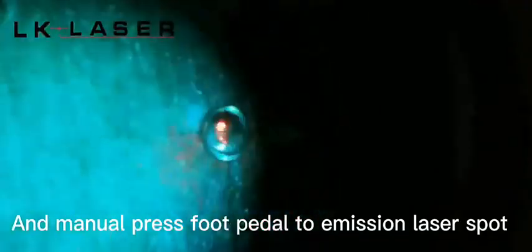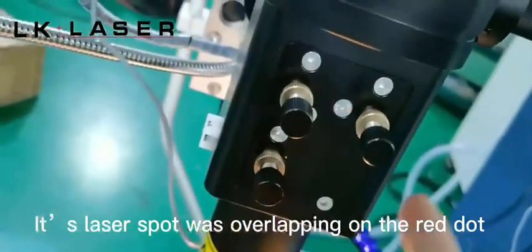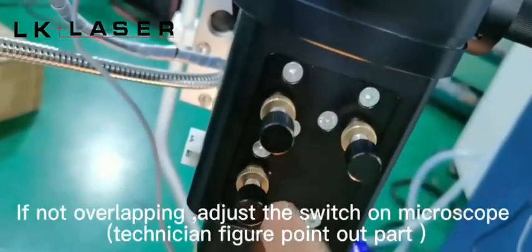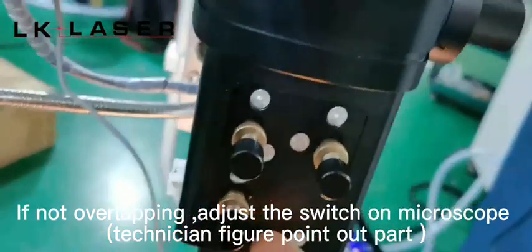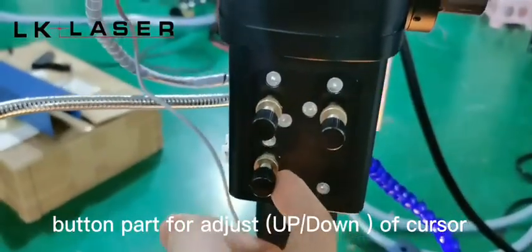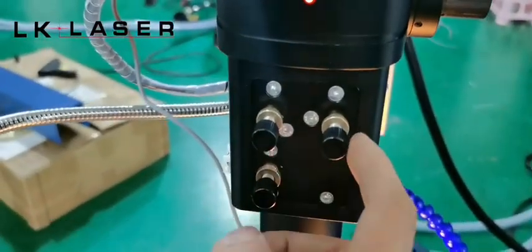And manually press the foot pedal to emit the laser spot. The laser spot should be overlapping on the red dot. If not overlapping, adjust the switch on the microscope. The bottom part is for adjusting the cursor up and down. The right part is for adjusting the left and right of the cursor.